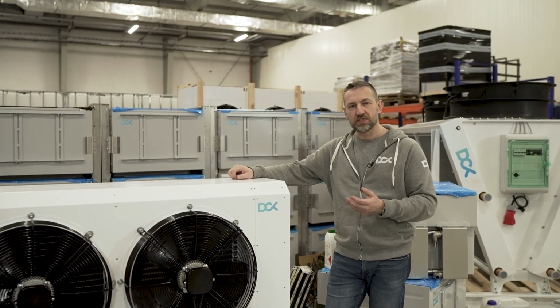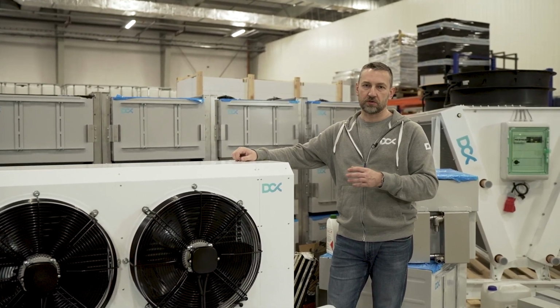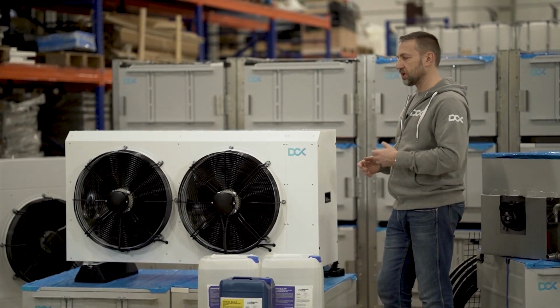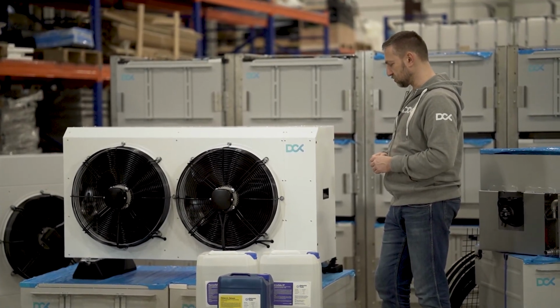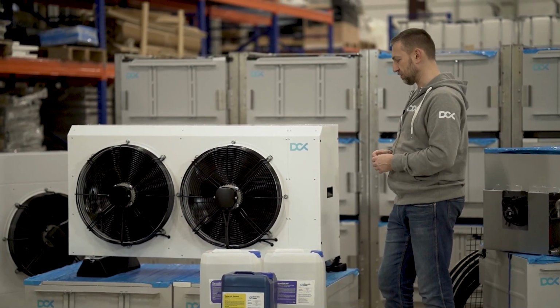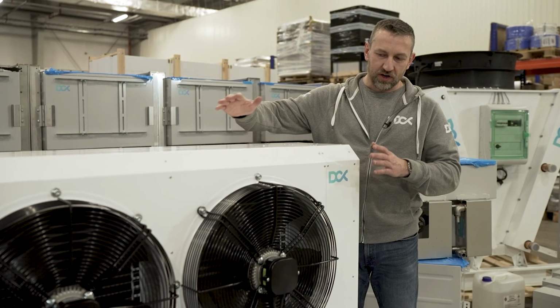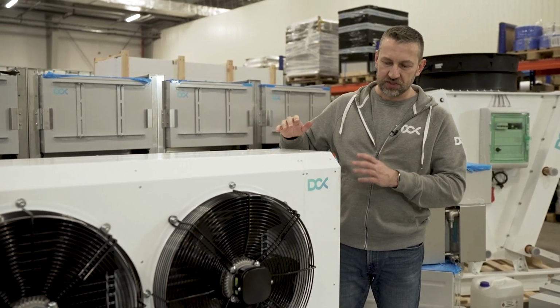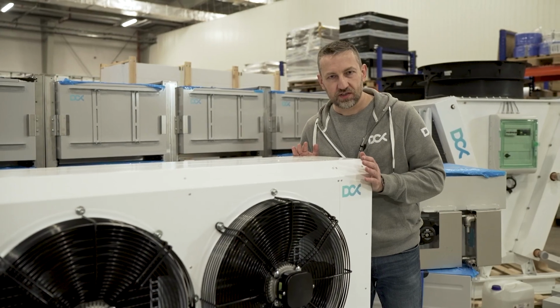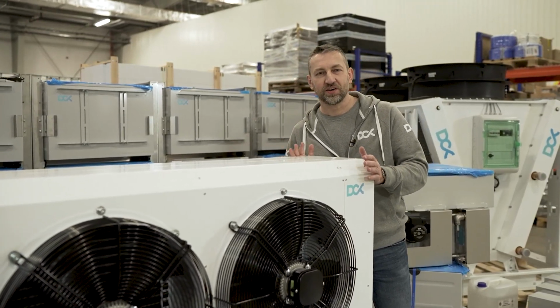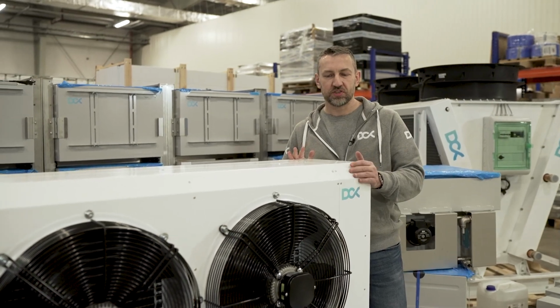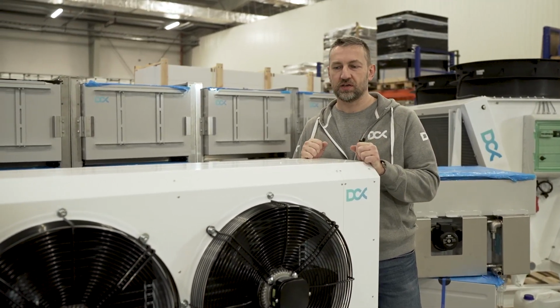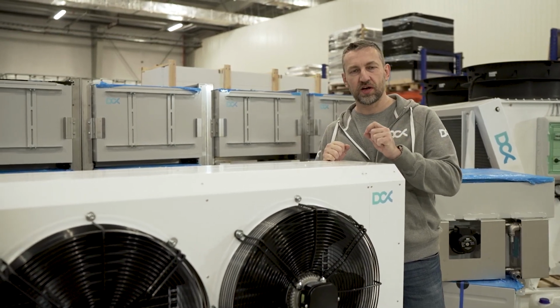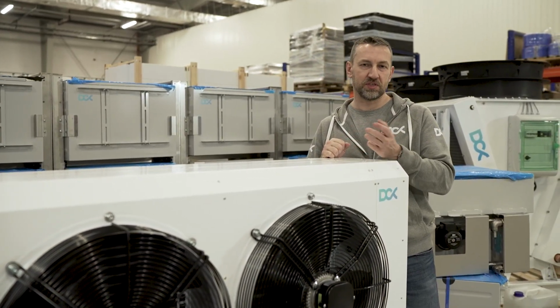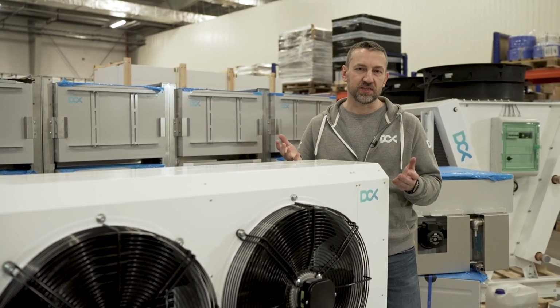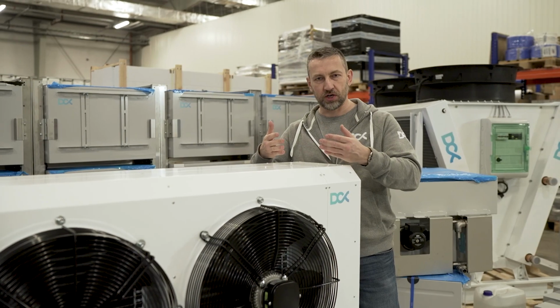It depends actually, because the system is equipped with a fan controller. The fan controller adapts to the ambient temperature and slows down the fans if we don't have to use the full capacity of the system. The dry cooler, or ICP40 integrated cooling and pumping system, must be located outside. So always outside, ideally on the north side of the building. It will reject up to 40 kilowatts of heat from your enclosure at 35 degrees Celsius ambient air, which means 95 Fahrenheit. So kind of summer days. During those summer days, it should reject 40 kilowatts of heat.